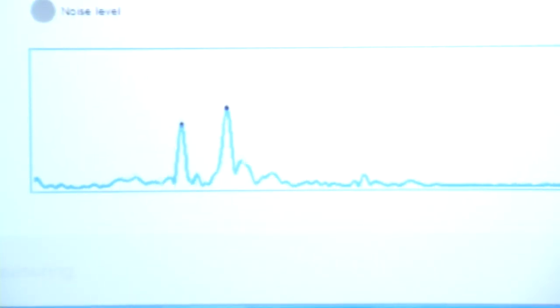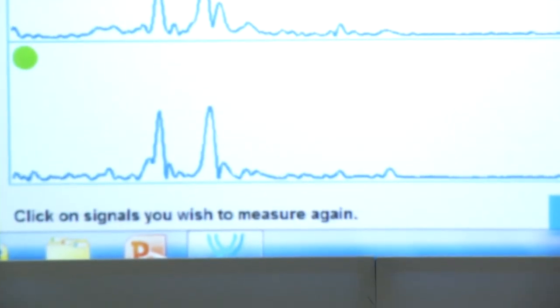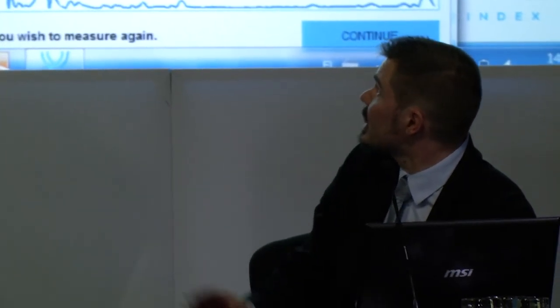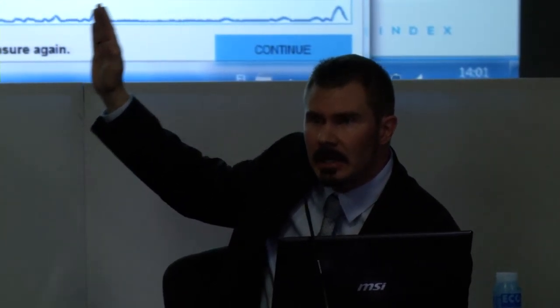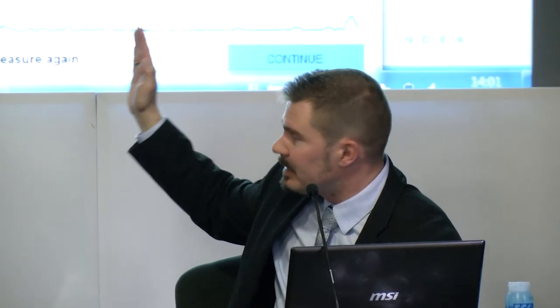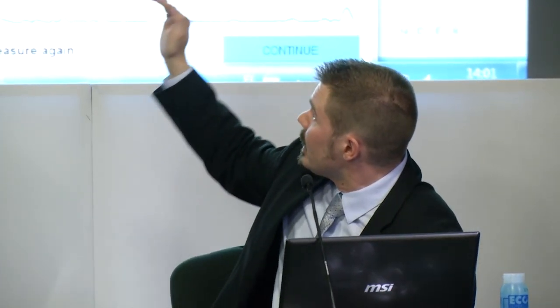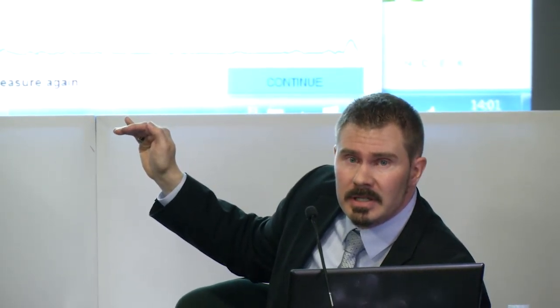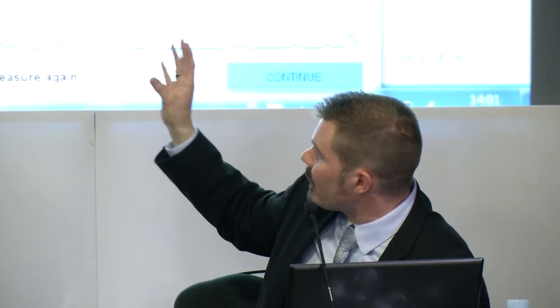With this, I repeat the measurement 5 times. We can see now those 5 measurements. The first echo comes from the upper surface, and the second from the inner surface, and the time difference tells us the thickness. Here are all 5 measurements, and in this phase we also make a statistical analysis comparing these measurements.